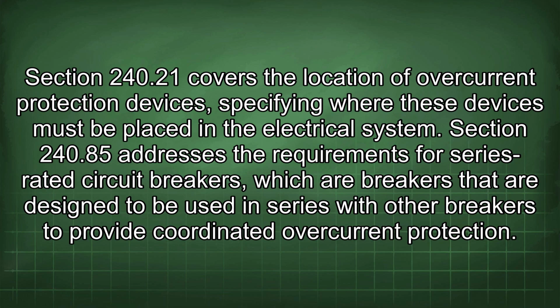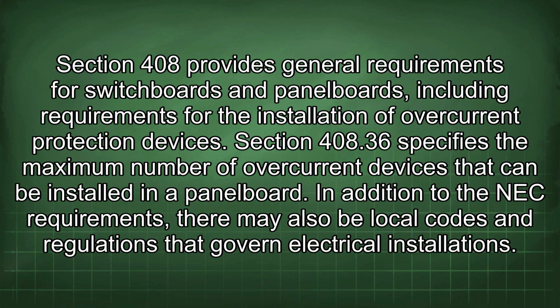Section 240.85 addresses the requirements for series-rated circuit breakers, which are breakers that are designed to be used in series with other breakers to provide coordinated overcurrent protection. Section 408 provides general requirements for switchboards and panel boards, including requirements for the installation of overcurrent protection devices. Section 408.36 specifies the maximum number of overcurrent devices that can be installed in a panel board.